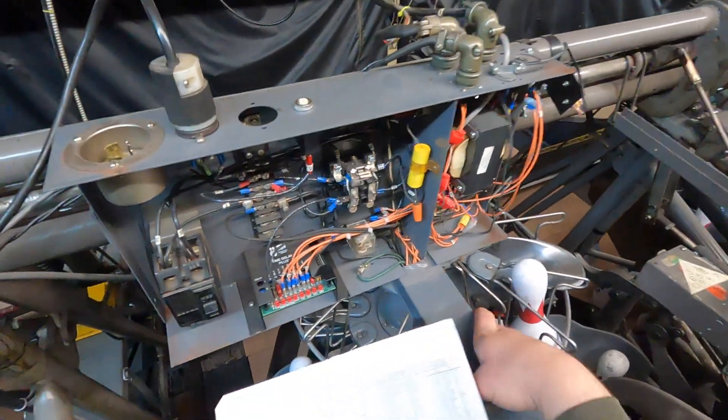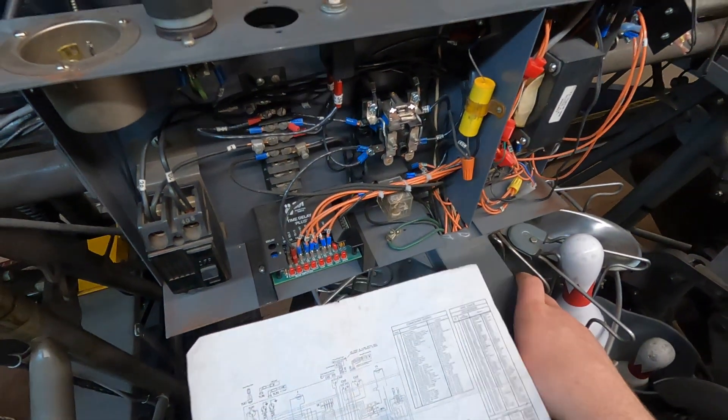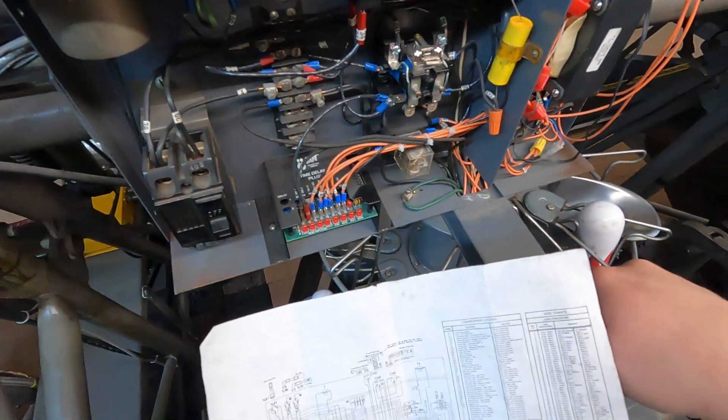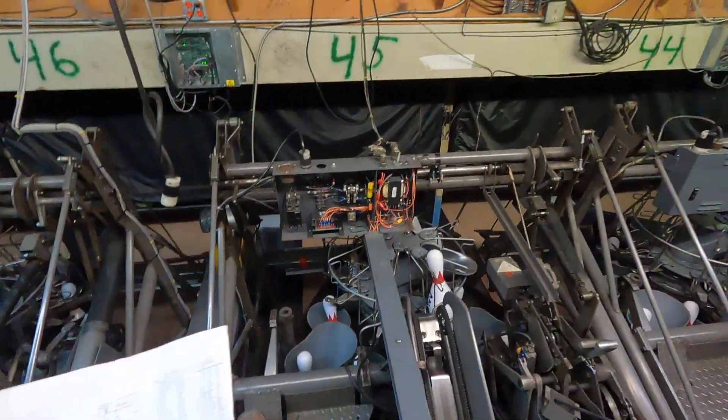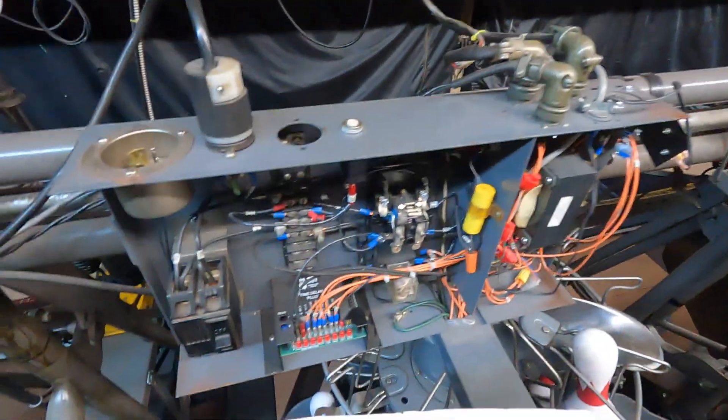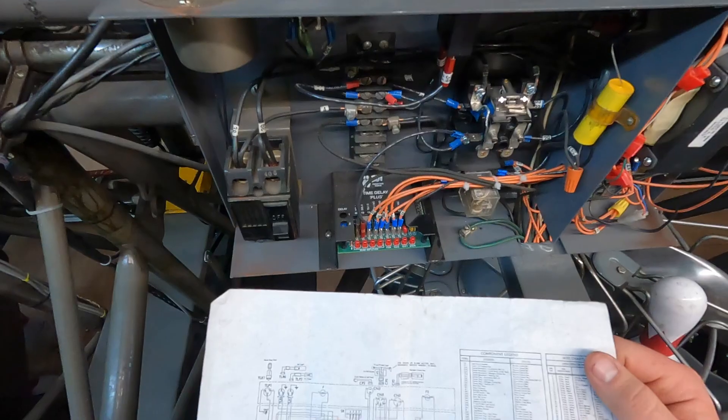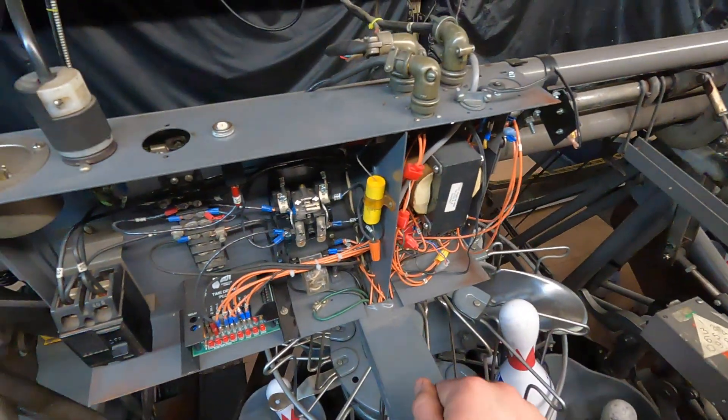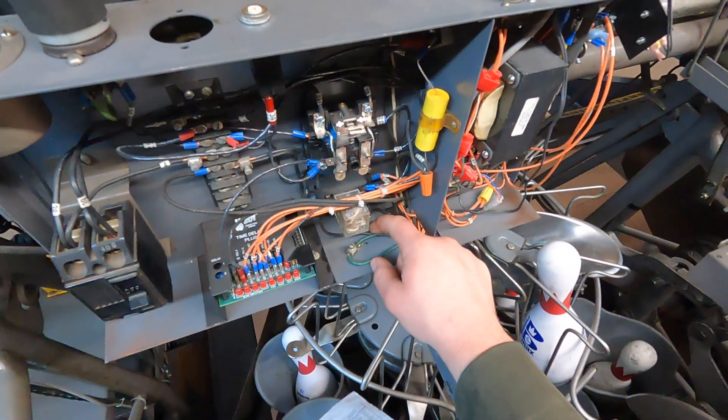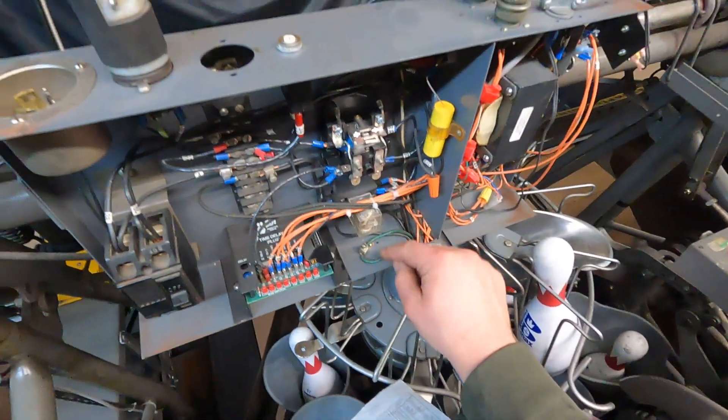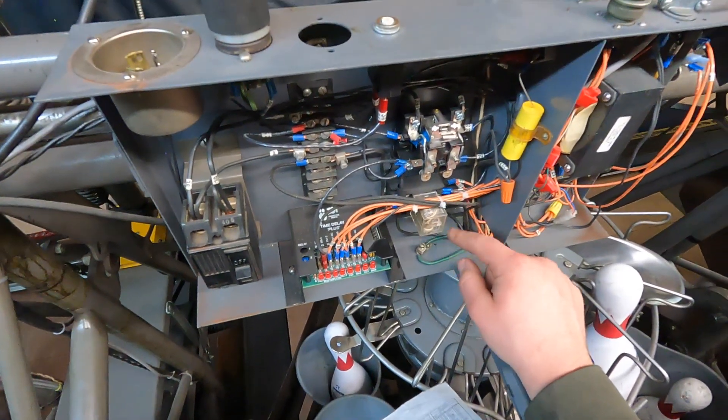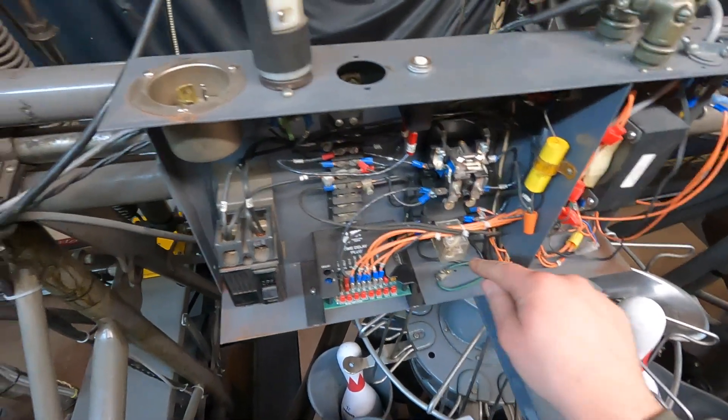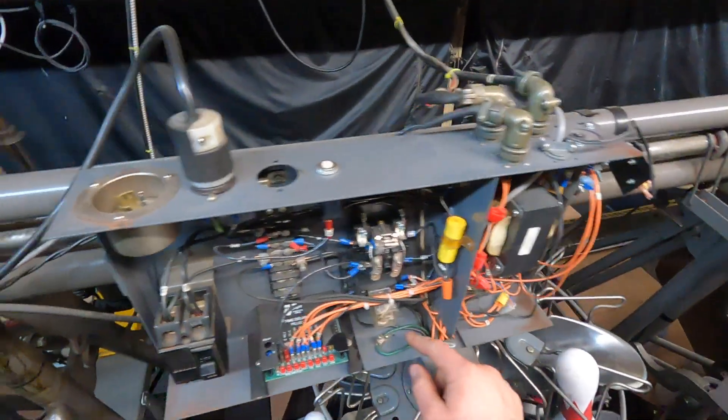So when you go and have that, I'm going to tell you what it hooks up to according to the schematic here. So you have wire 27 that comes out of there. That's your ground wire. Ground wire is going to hook up to here and it's going to go through here and it's going to go and connect to the same place that your motor ground wire connects to.